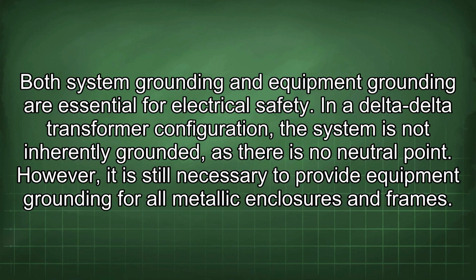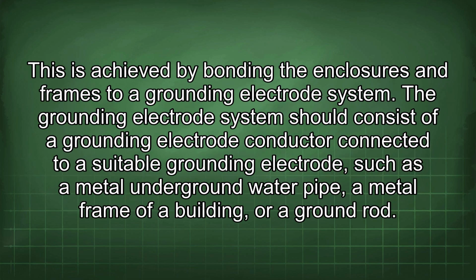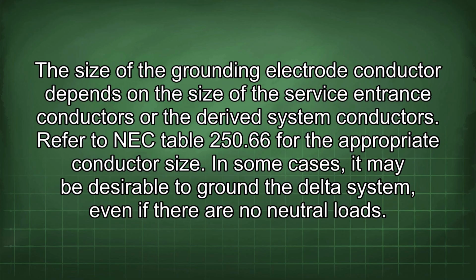In a delta-delta transformer configuration, the system is not inherently grounded, as there is no neutral point. However, it is still necessary to provide equipment grounding for all metallic enclosures and frames. This is achieved by bonding the enclosures and frames to a grounding electrode system. The grounding electrode system should consist of a grounding electrode conductor connected to a suitable grounding electrode, such as a metal underground water pipe, a metal frame of a building, or a ground rod. The size of the grounding electrode conductor depends on the size of the service entrance conductors or the derived system conductors.